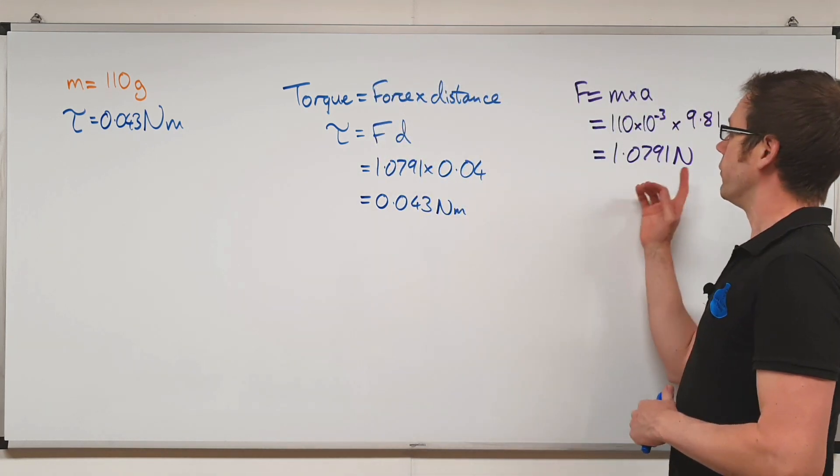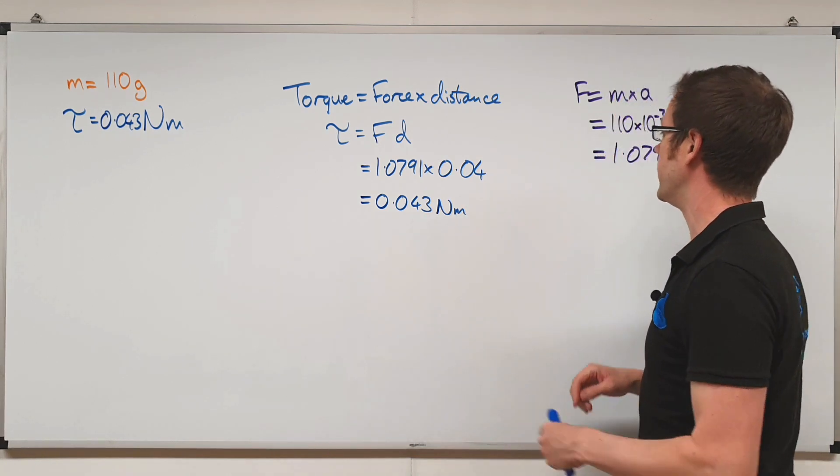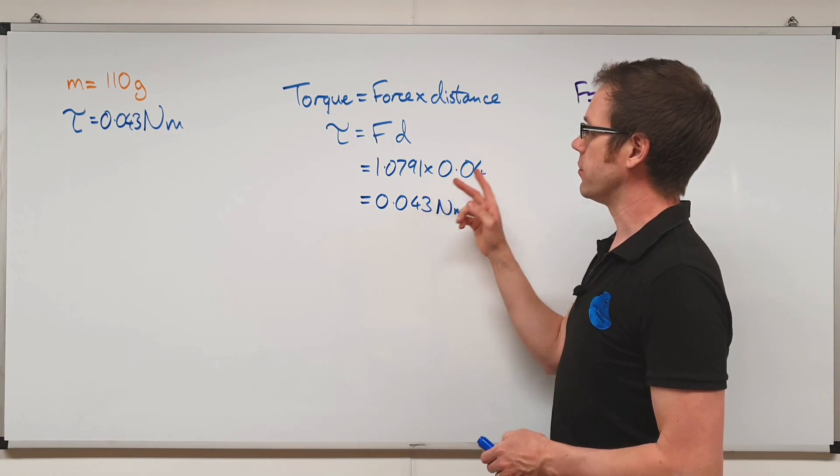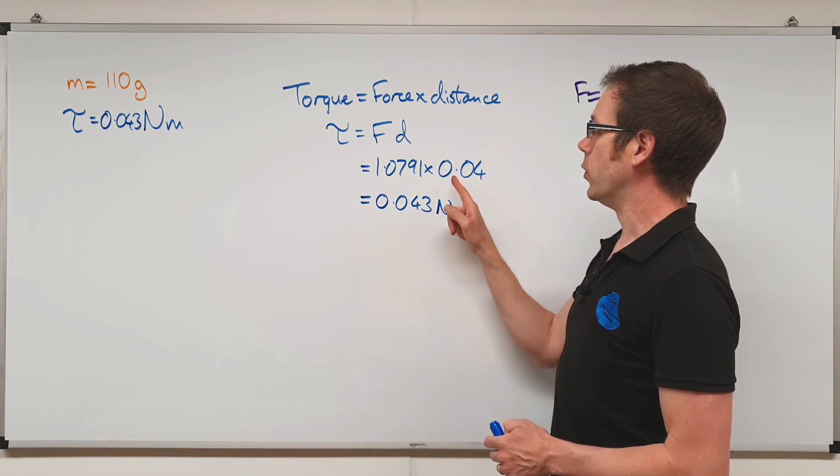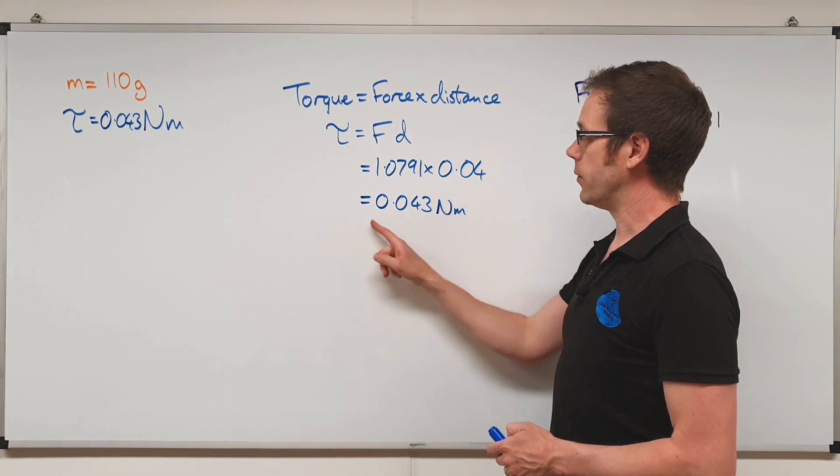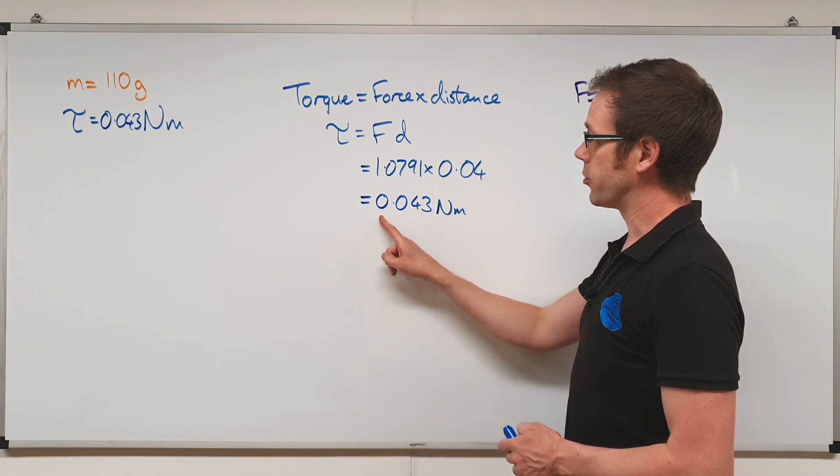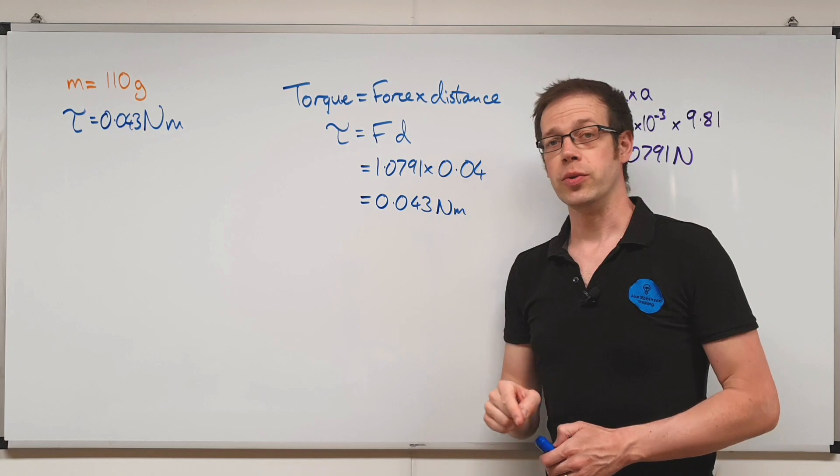We figured out what force it's exerting. We've done that by taking the mass measurement from the scale and converting it into a force reading. And then we times that by the distance from the axis of rotation. So in this case it's four centimeters or 0.04 meters. And when we do that, we find that this motor, once we ran this off, is creating a torque of 0.043 newton meters.